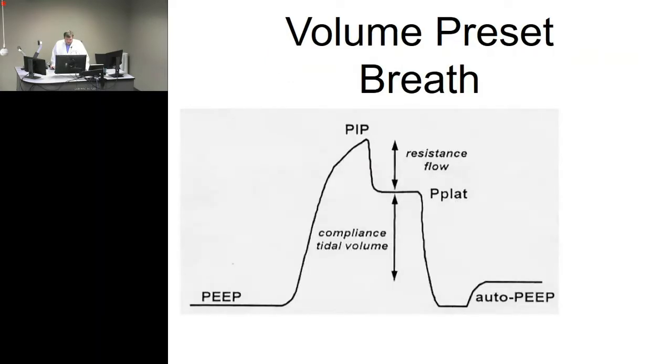So this is kind of just a graphic that gives us information on what we're used to seeing. Once we talk about our general settings, a lot of the ways that we monitor things are on flow volume curves, so pressure curves, volume curves, and flow curves. And this is a pretty standard readout, easy to view, of what you'll standardly see.